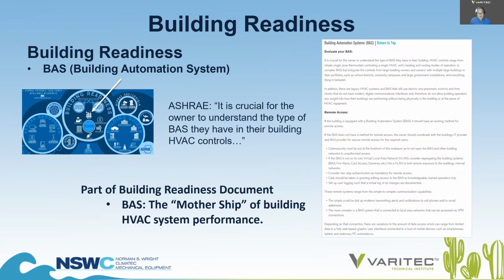ASHRAE says it is crucial for the owner to understand the type of BAS they have in their building HVAC controls. Why? Well, the building automation system is the mothership of your building HVAC system performance. So you want to make sure that your BAS is operating properly and that it is controlling the system in a way that ASHRAE's standards and design intents are being met.